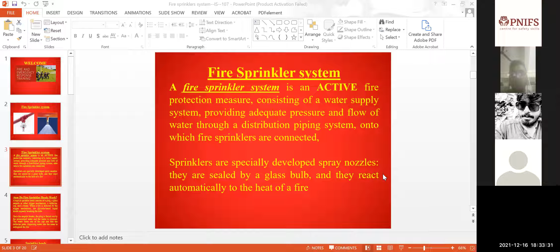Triggered mechanism: how the fire sprinkler heads work. The fire sprinkler head consists of a plug, a glass ampule or other trigger mechanism, a deflector cap, and a frame. When fire is detected by the trigger mechanism, the glycerin-based liquid inside expands, breaking the tube, and once the ampule breaks, the plug is forced out.